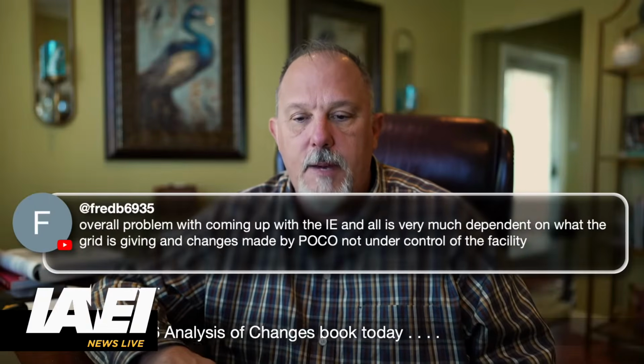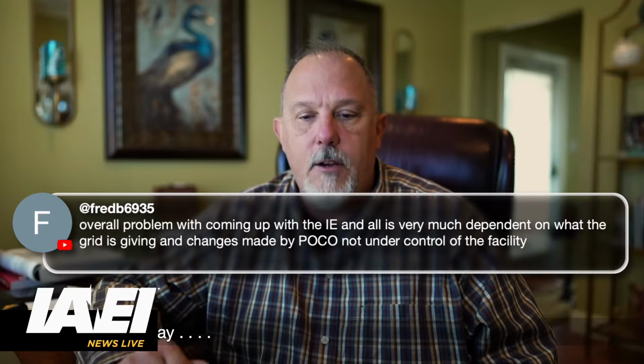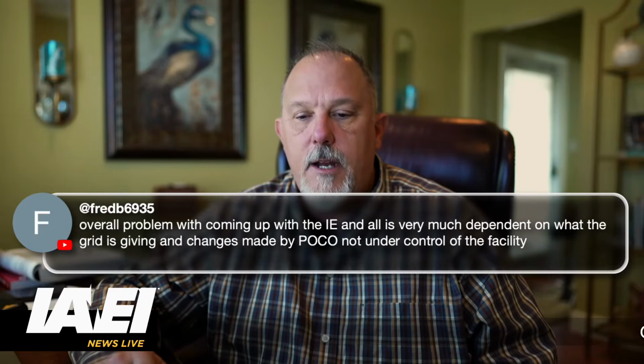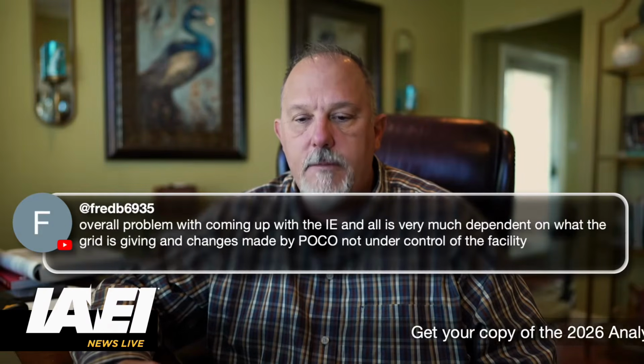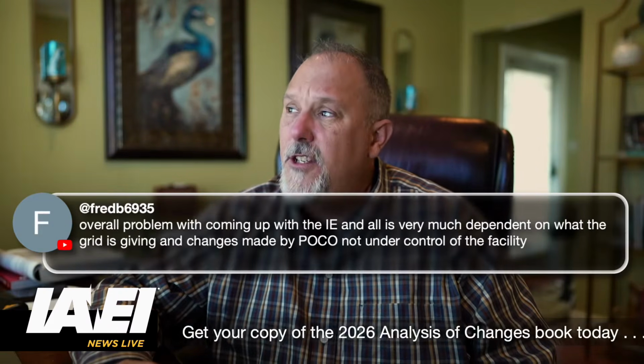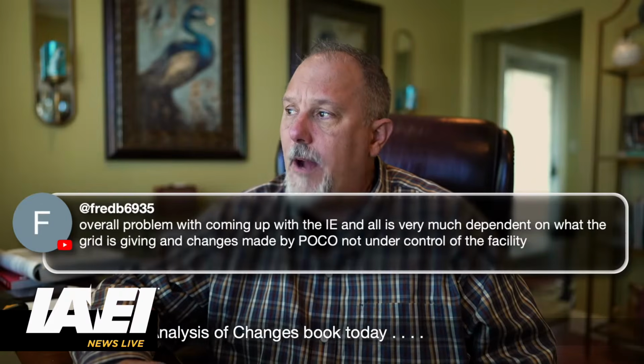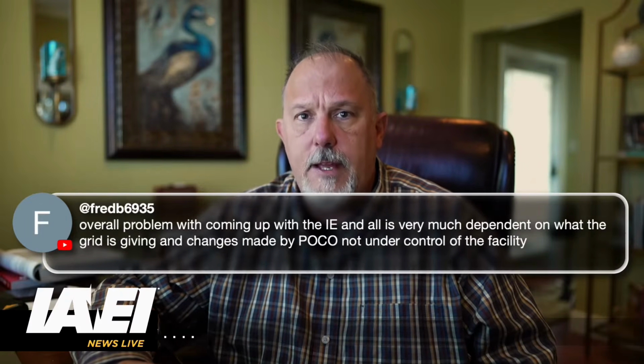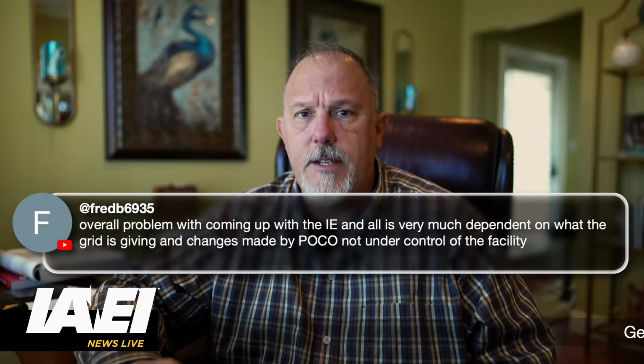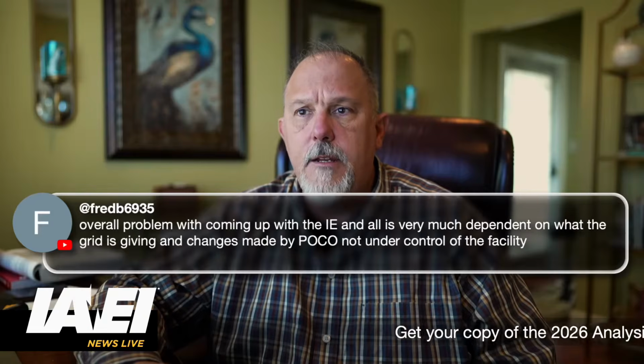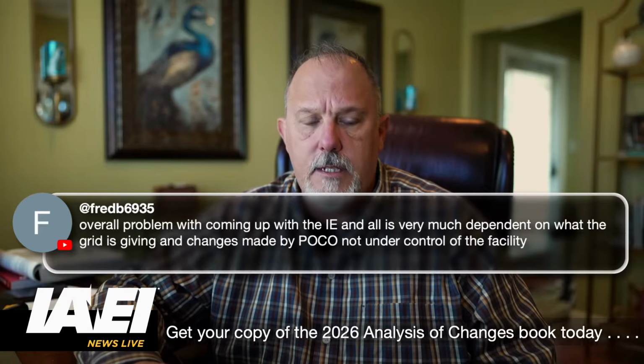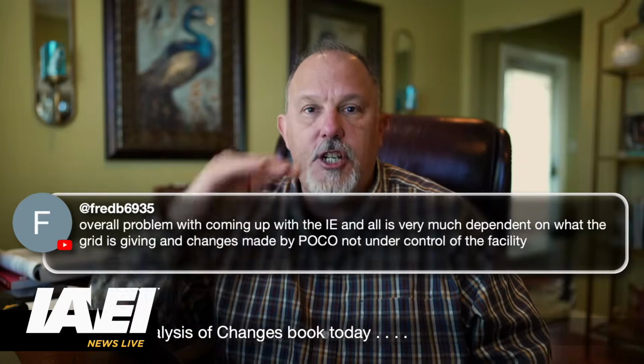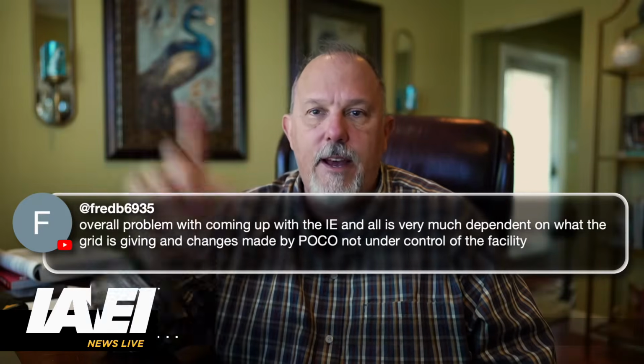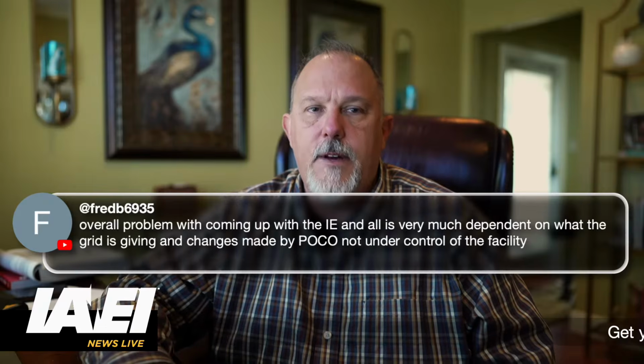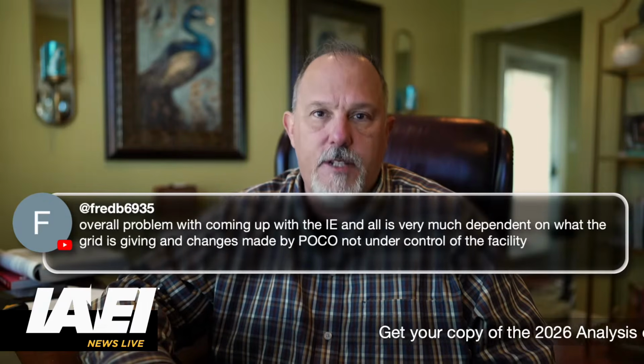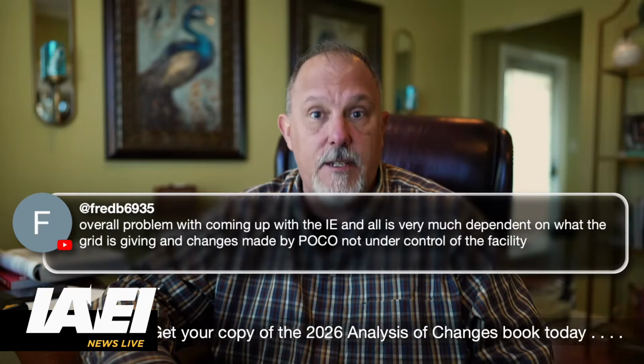Freddie B: overall problem with coming up with the incident energy is very much dependent on what the grid is giving and changes made by the public utility, not under the control of the facility. So there are ways around that. There's an IEEE paper that tells you how to address when the utility doesn't give you the actual fault current, but changes and fluctuations in the current when you have a big hunk of iron sitting there like a transformer, especially in those cases.